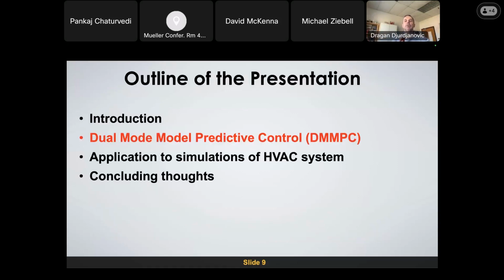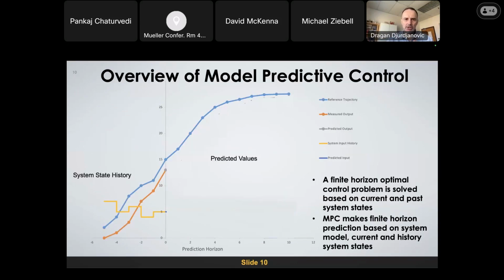That being said, I want to talk about this methodology, which is a variation of model predictive control. Model predictive control is a methodology that many of you have likely heard of, where we use data that we are collecting, the history of system states and the history of our control inputs, and maybe add on top of it a model of the system. With HVAC systems, we have models of the room we are cooling, as well as models of our HVAC equipment. Then, knowing what we wish to achieve, say desired temperatures in the room, we can optimize our control signals up to a certain horizon to make sure that the predicted outputs converge to where we wish to be.